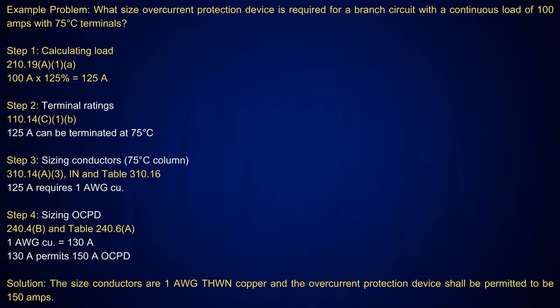Okay. Well, we got a branch circuit that has a continuous load of 100 amps. What do you take it at? 125% gives me 125 amps. The next size above that is 130 amps. And table 310.16 come across, it's going to tell you it needs a number 1 conductor. I'm going to protect the conductor in this case, which is going to be a 150 amp overcurrent protection device.